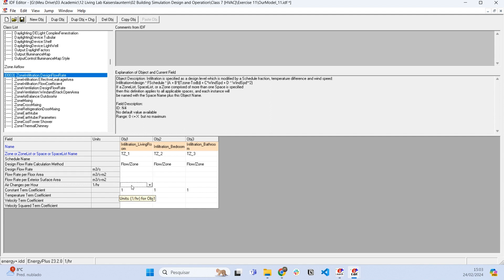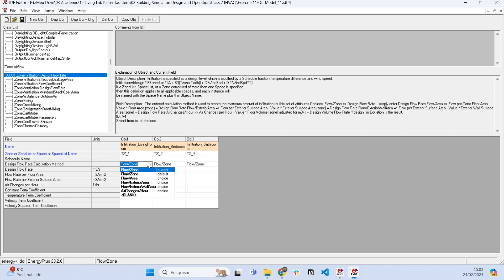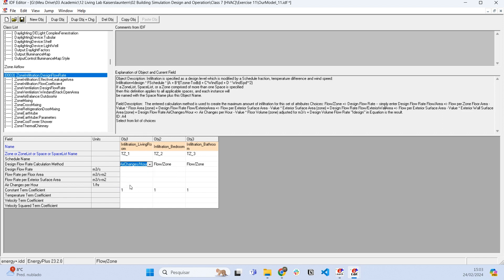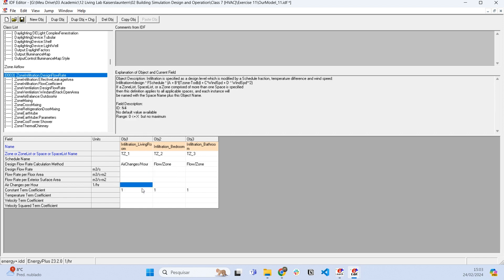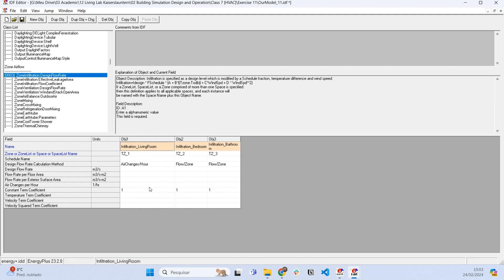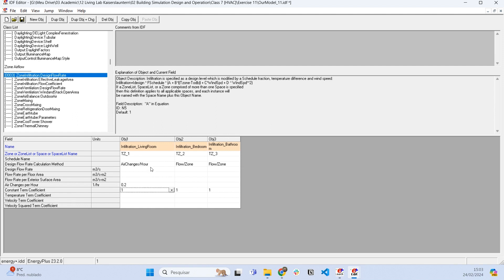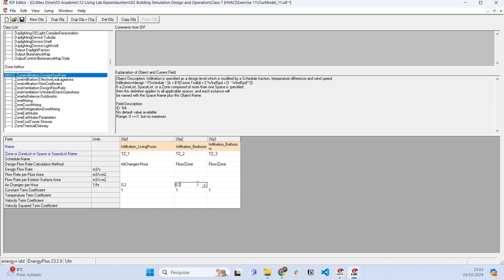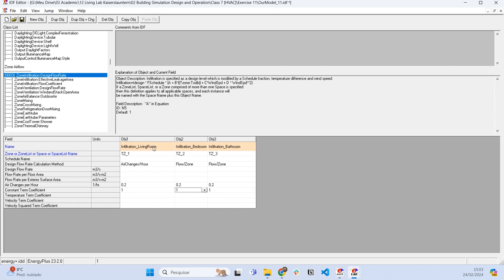Let's use air changes per hour for this example. I'm going to say that the infiltration of the living room is going to be around 0.2 air changes per hour, and let's say the same thing for the bedroom and the bathroom.